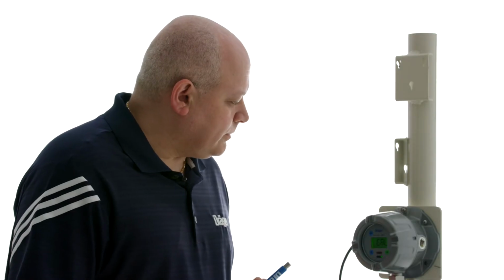As we move along, we now have a calibration signal that you can set. So once the unit goes into calibration mode, it will send out a specific signal below 4 milliamps, and that could be adjusted such that your controller realizes that the detector is in calibration mode and will not go into a fault or an alarm state.